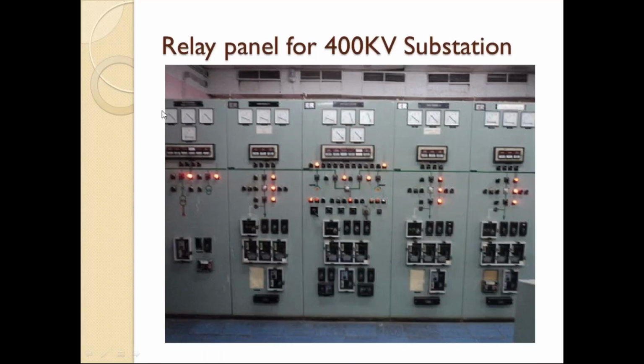So for CT we use 2.5, and for the trip relays and controls we will give 1 mm² size cables. But if you are connecting from panel to nearby panels, we will use a bus wire. There is a bus wire slot located above, and through it they will connect a bus wire if it is a nearer panel. So if the first and second panels are near and any connection needs to go from one to the other, they will connect a bus wire. If I want to go to a third or fourth panel, we will route a cable.